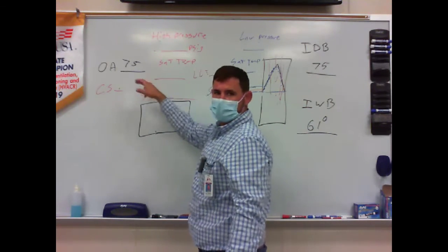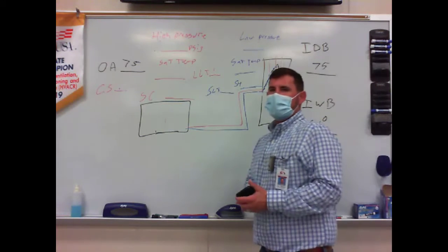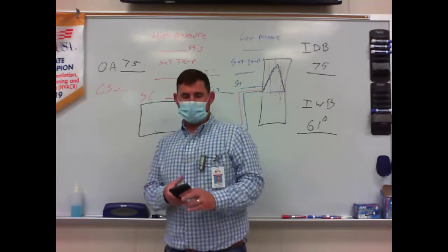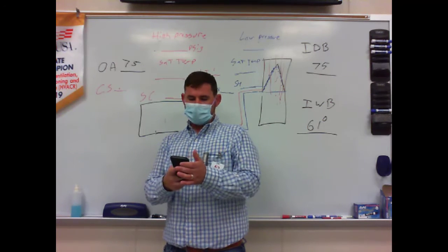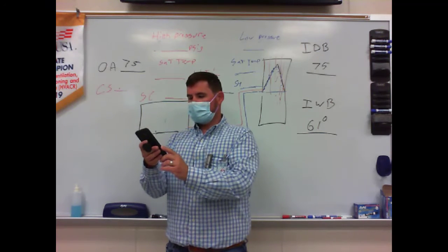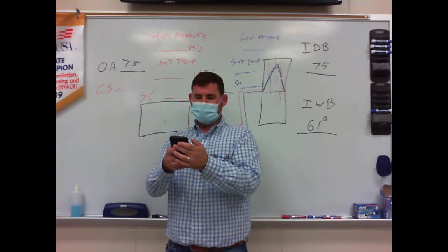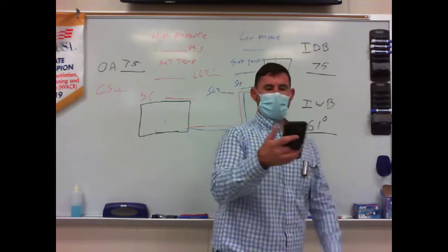75 degrees, right? So I use a check and charge chart. It's called a superheat chart. This one is Emerson check and charge. I'm going to tell it we're 410A. And I'm going to say superheat non-TXV.